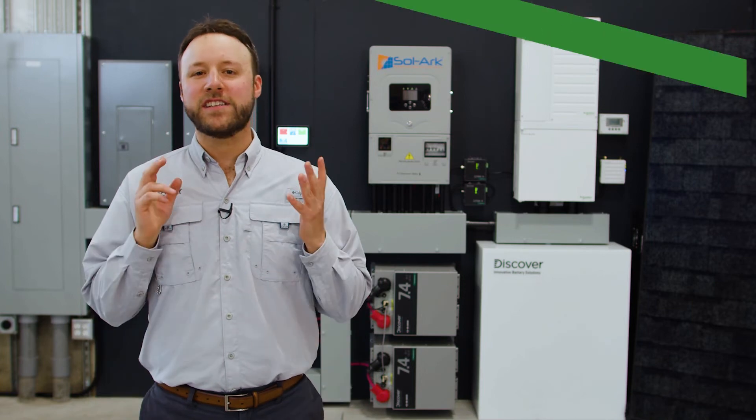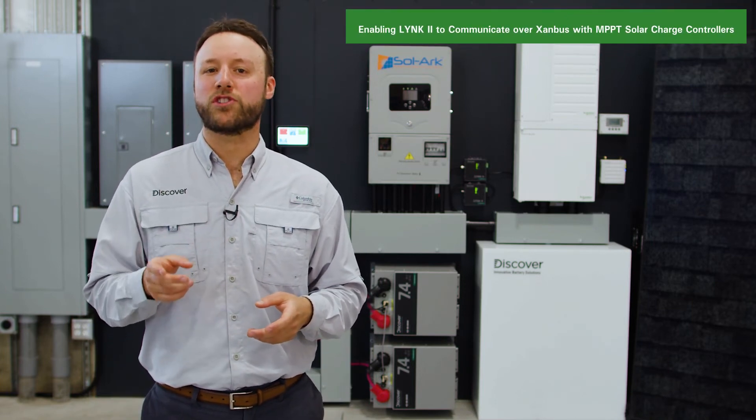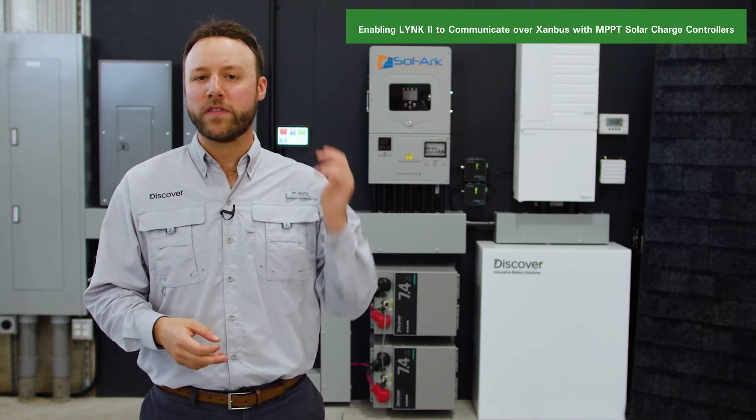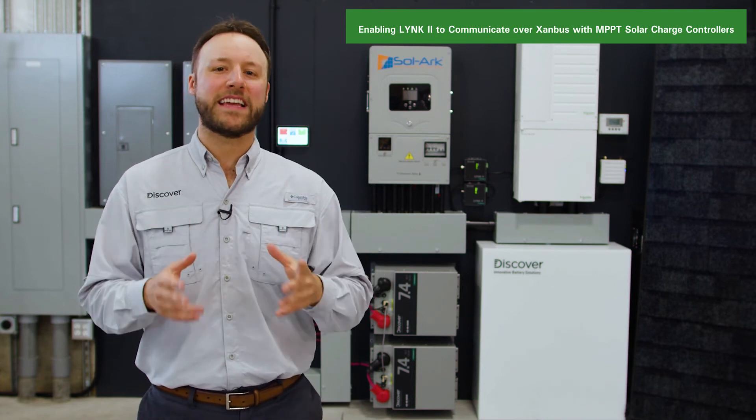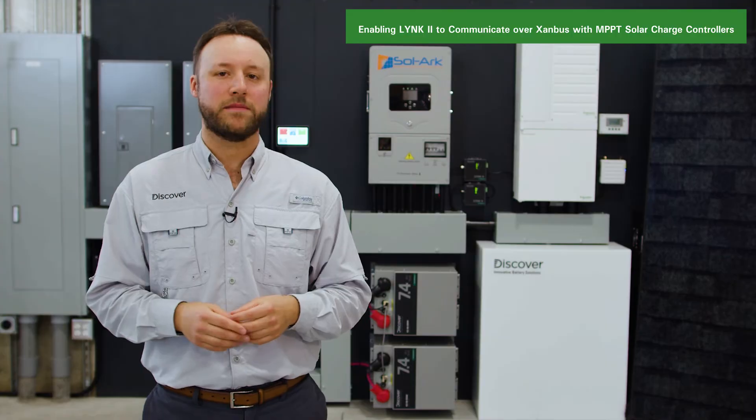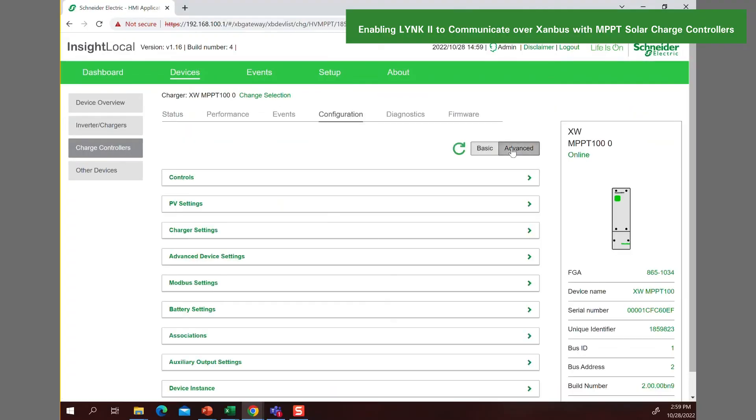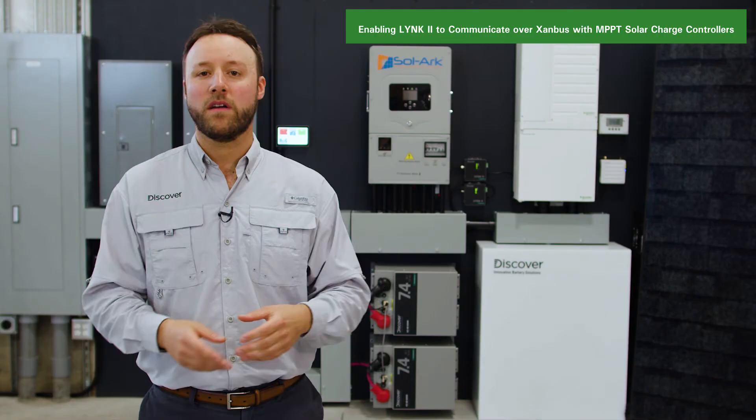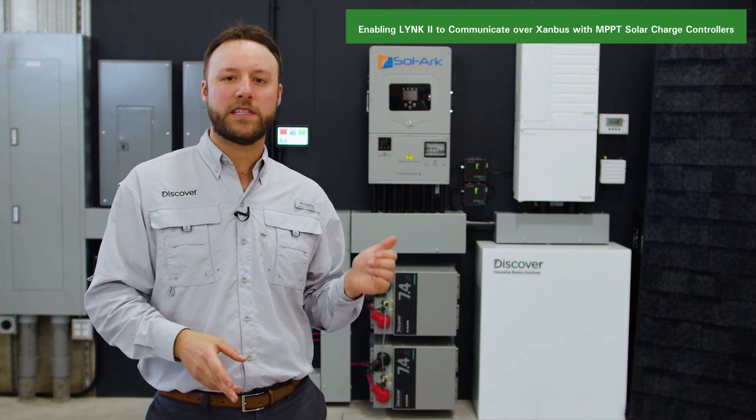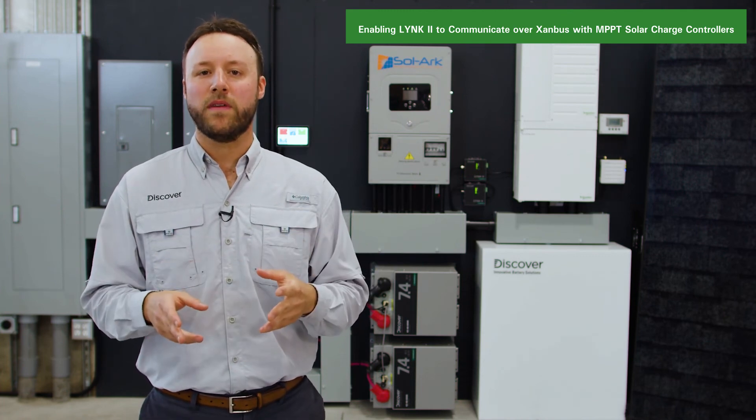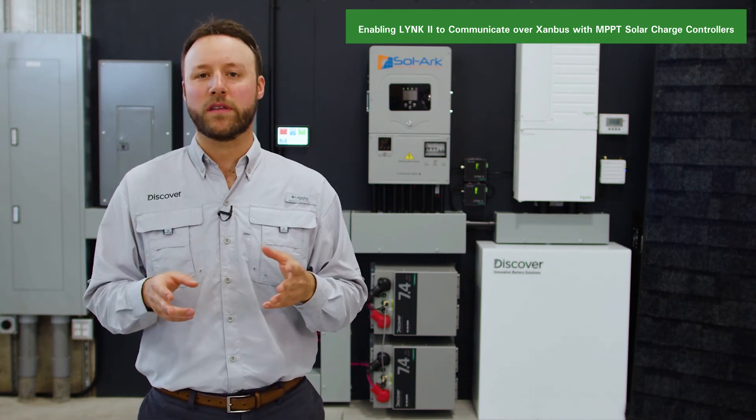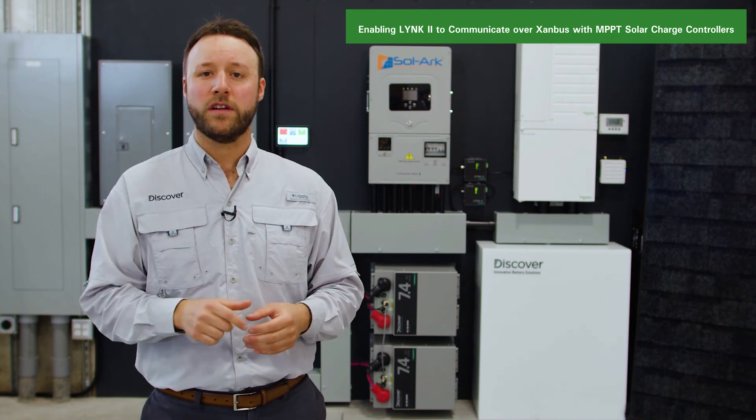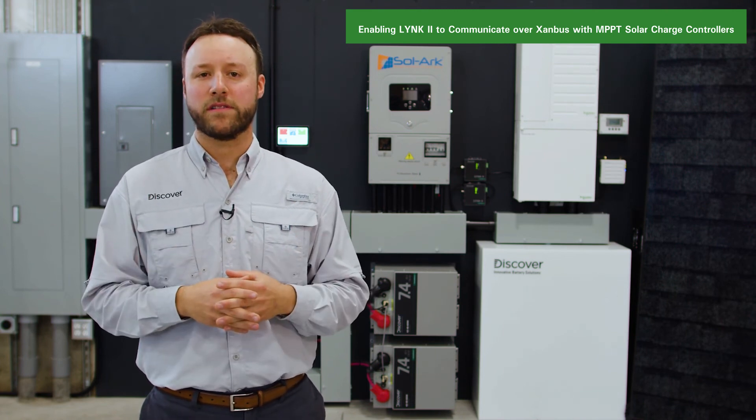In addition to the XW Pro, Schneider MPPT Solar charge controllers can be programmed to communicate with the Discover batteries via the LYNK II Gateway over Xanbus. Using Insight Local, navigate to the battery settings and the charger settings for the MPPT Solar charge controller. All the battery and charger parameters for the MPPT are user adjustable and must be set appropriately to interact correctly with the XW Pro inverter charger and the Discover Lithium batteries.